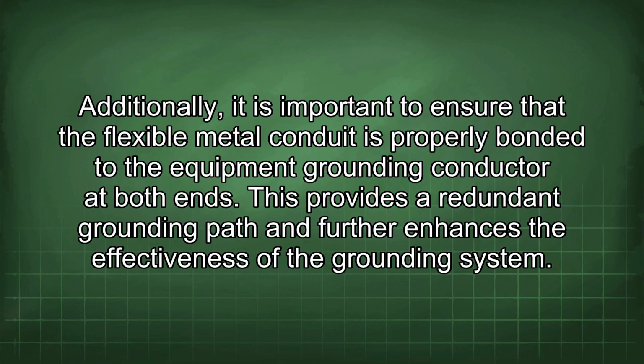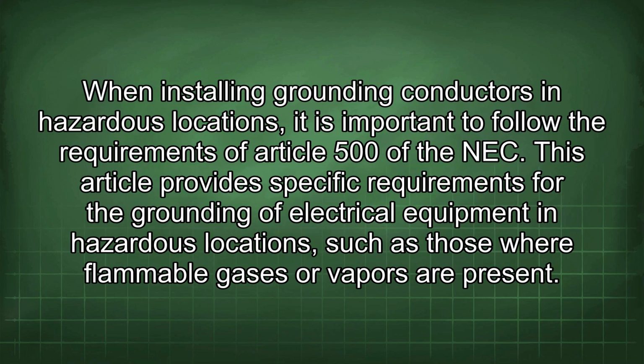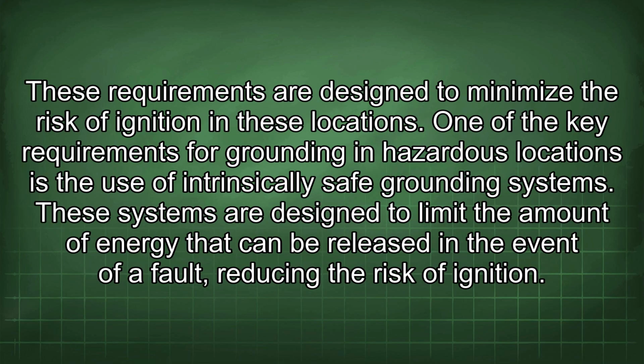Additionally, it is important to ensure that the flexible metal conduit is properly bonded to the equipment grounding conductor at both ends. This provides a redundant grounding path and further enhances the effectiveness of the grounding system. When installing grounding conductors in hazardous locations, it is important to follow the requirements of Article 500 of the NEC. This article provides specific requirements for the grounding of electrical equipment in hazardous locations, such as those where flammable gases or vapors are present. These requirements are designed to minimize the risk of ignition in these locations.